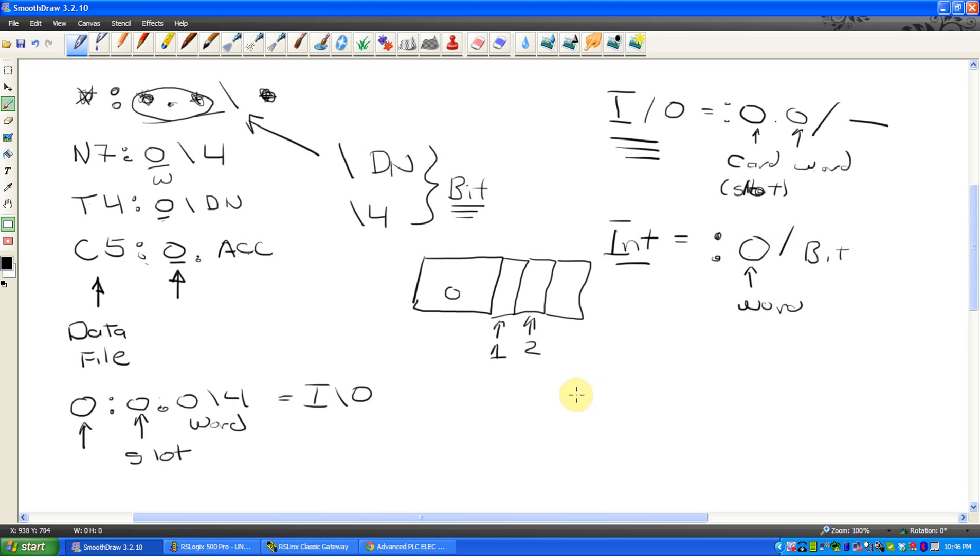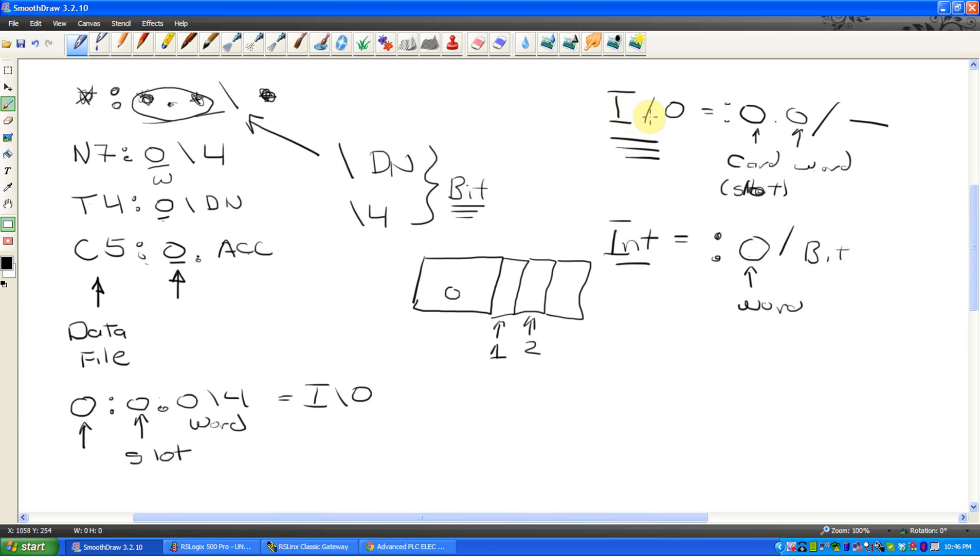But it's really not as complicated as it sounds. I mean, the first character before the colon's your data file, after a slash, it's always, always, always a bit. The only thing that can change is because when it's real world IO, word doesn't cut it. We have to say which card and then define the word. If it's internal, there is no card, so it's just word then bit.